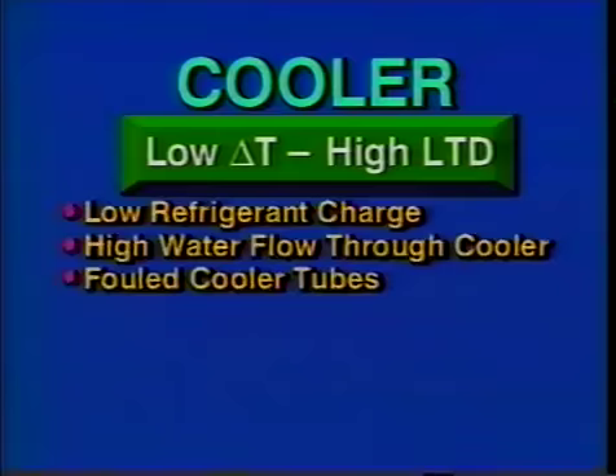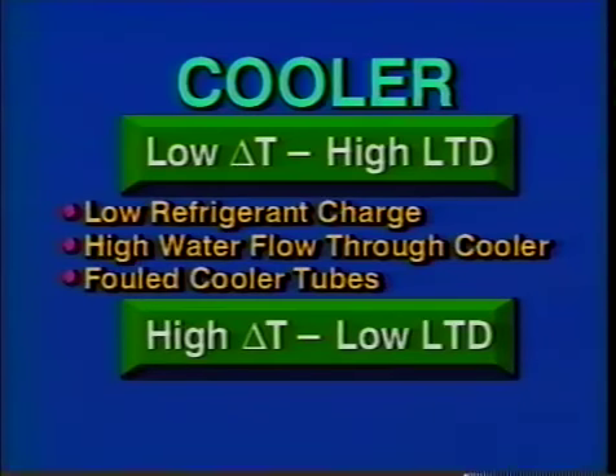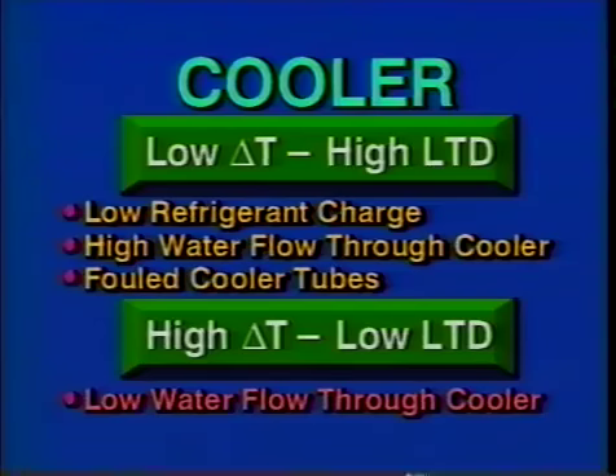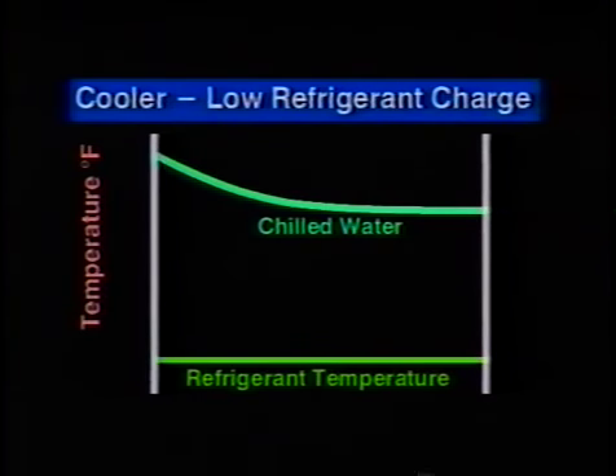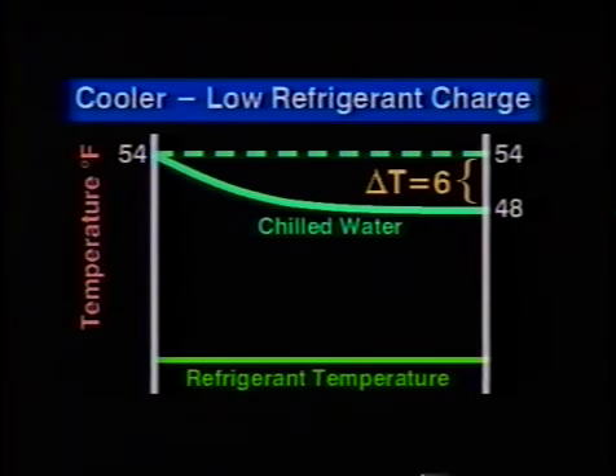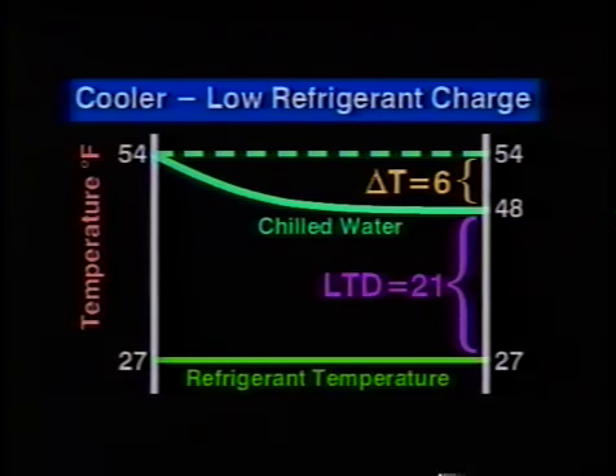When compared to design temperature, a low delta T and a high LTD could indicate a low refrigerant charge, high water flow through the cooler, or fouled cooler tubes, while a high delta T and low LTD would indicate low water flow through the cooler. Let's look at an example where the return water is 54 degrees Fahrenheit and the leaving water temperature is 48 degrees. This gives us a delta T of 6 degrees across the cooler at full load. The cooler refrigerant pressure is 51 psig, which corresponds to a saturated cooler temperature of 27 degrees. Our LTD is now 21 degrees, a sure sign of trouble. The reduced heat transfer from the water to the refrigerant and the low refrigerant pressure indicates a low refrigerant charge. A check on the suction superheat will also likely be higher than design.